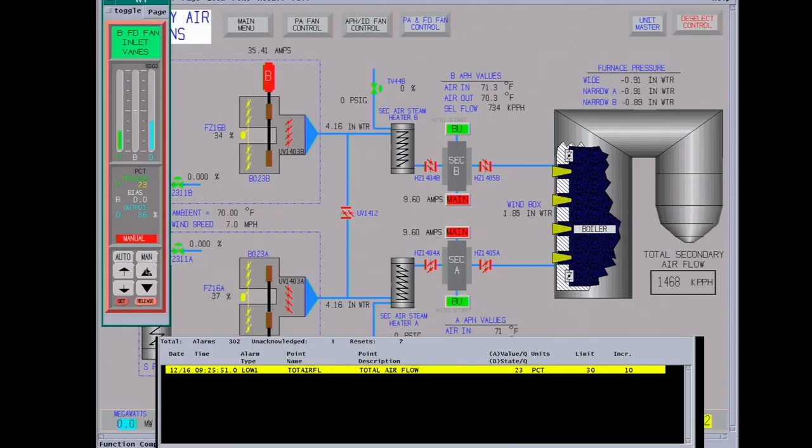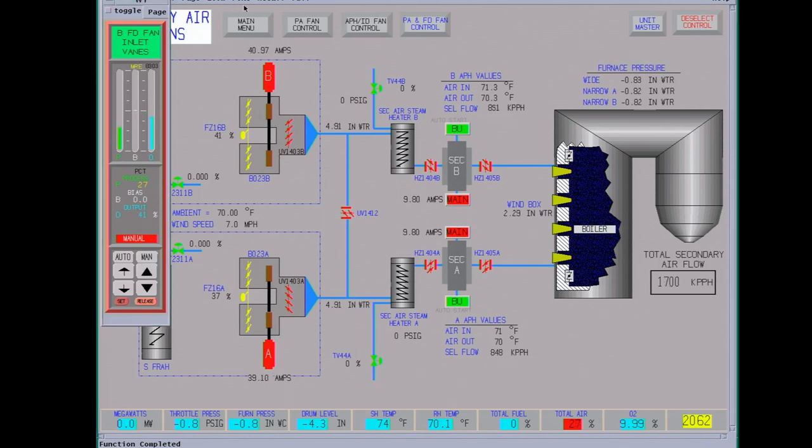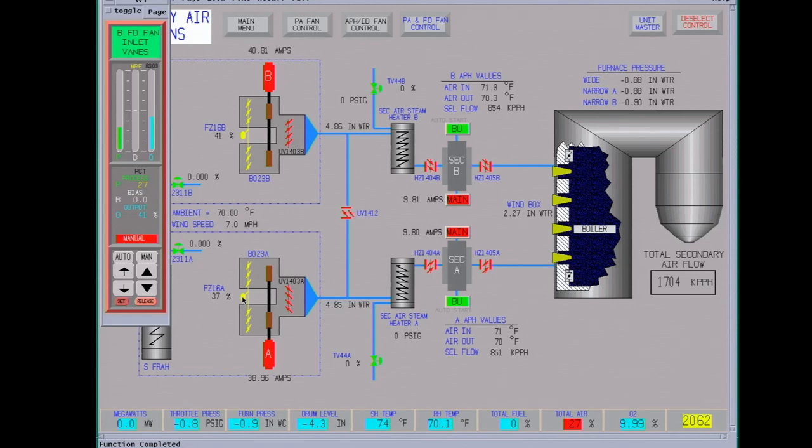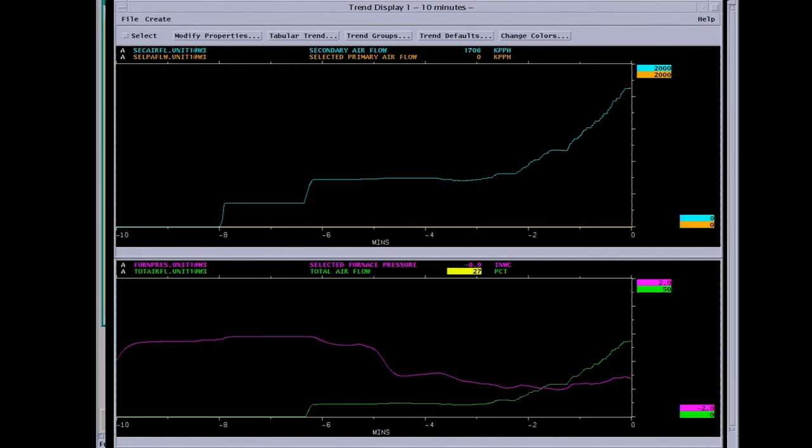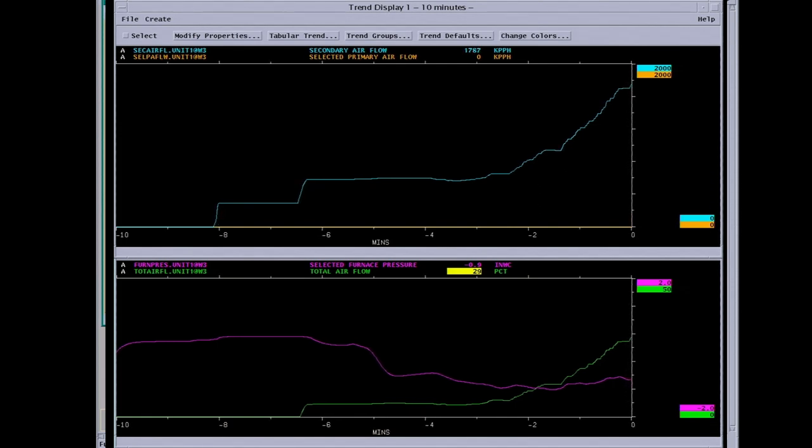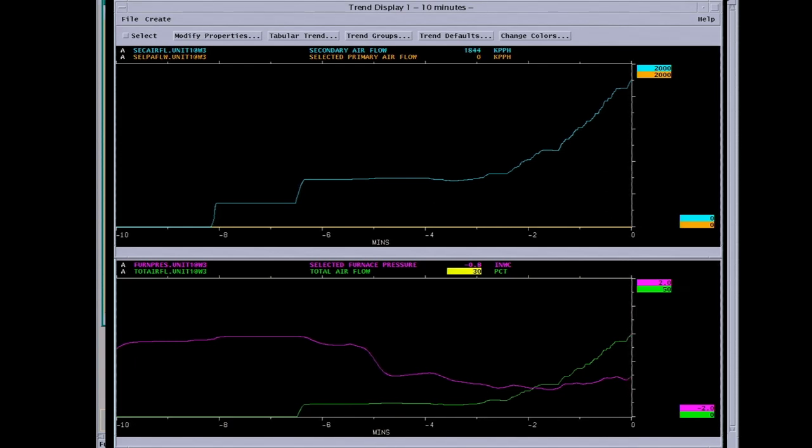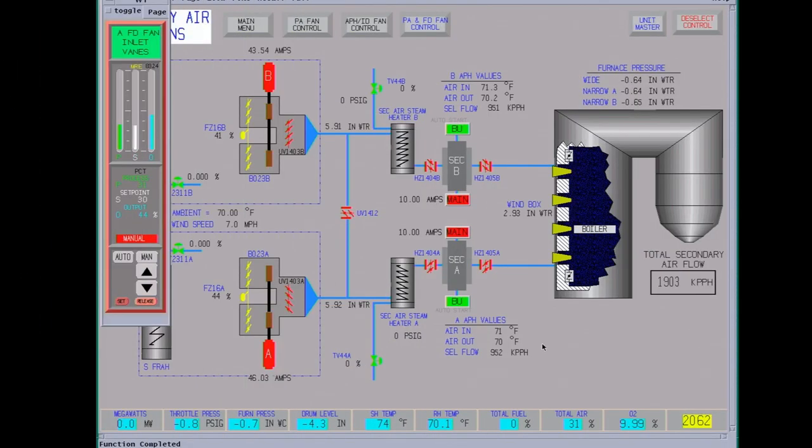Okay, we just got the low, low alarm in on the air, so we're gaining. We're up to about 40 amps on this fan. Basically we want both fans to be pretty similar. We won't put these in auto until we're done purging. It's always a good idea to put stuff in auto as soon as you can, otherwise it gets forgotten. Okay, we're above 31.